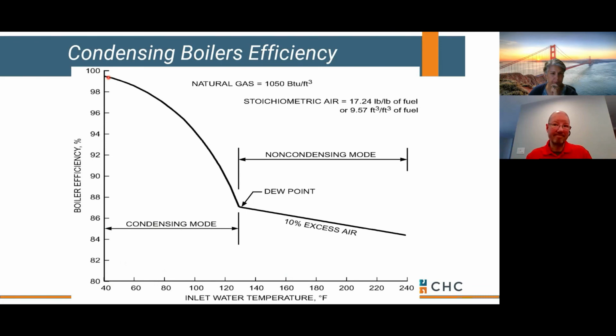If you're non-condensing, your materials of construction can't handle the acid you would get with low return temperatures. So now you're limited on the return temperature that the water heater or boiler can handle. Typically for most manufacturers, that's about 130 degrees. If you're cast iron sectional, it's about 140. But if you're non-condensing, make sure you read the O&M because it's going to tell you what the minimum return temperature should be and not to go below it. It's all based on efficiency, but a lot of that has to do solely with return water temperature and the materials of construction. I hope that helps answer the question a little bit. If not, shoot us an email. Happy to address that further.